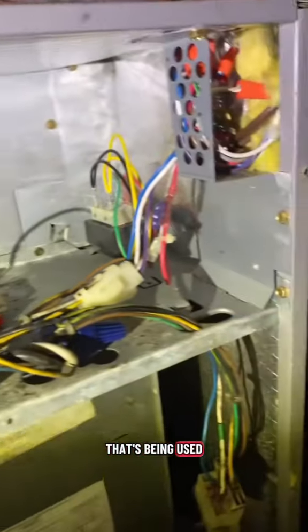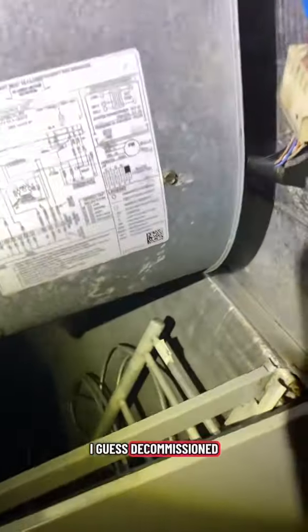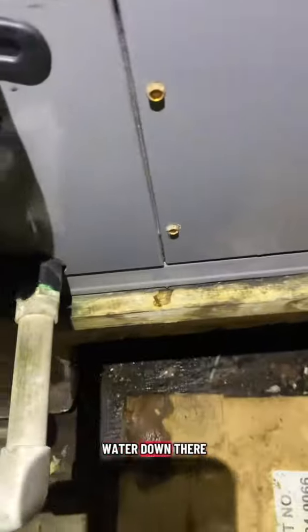Immediately walking up to the unit, I noticed it did not have a P-trap. Also, from the look of everything, it almost seems like this location needs two systems to cool it properly, but this is the only unit being used — the other one is decommissioned. You can see all that water down there, so the P-trap is most likely the reason it's leaking.